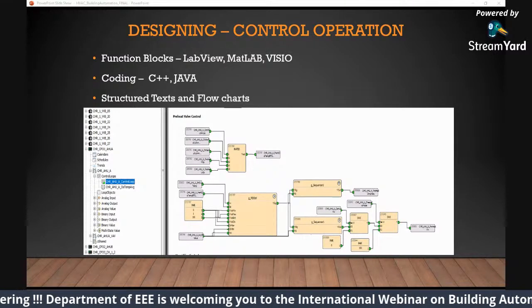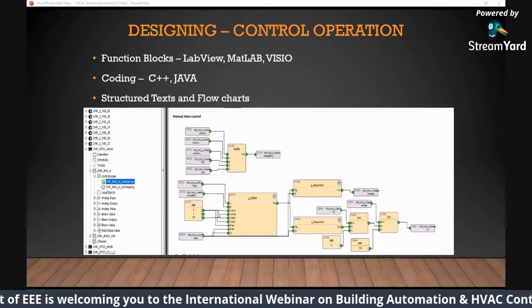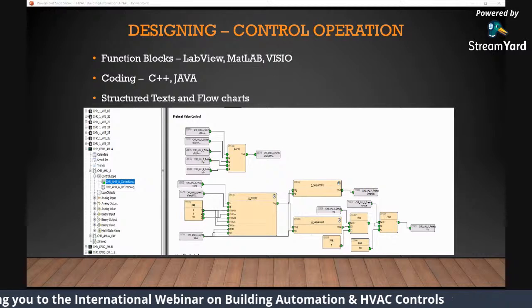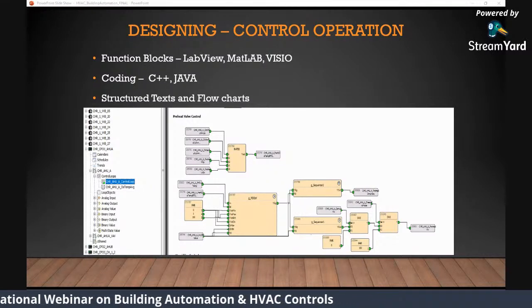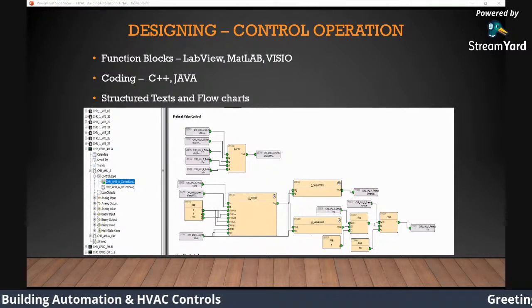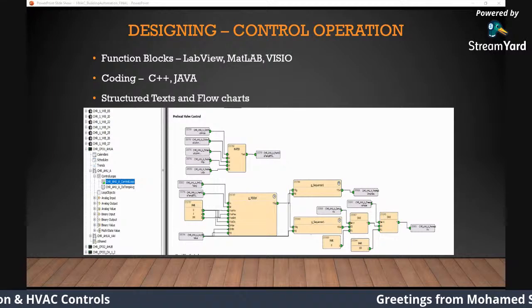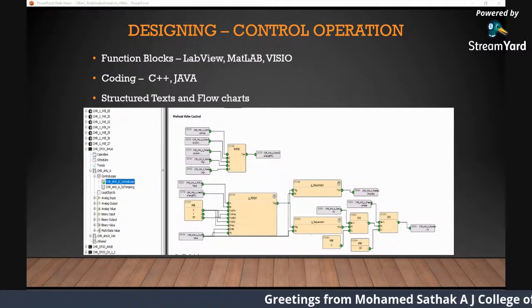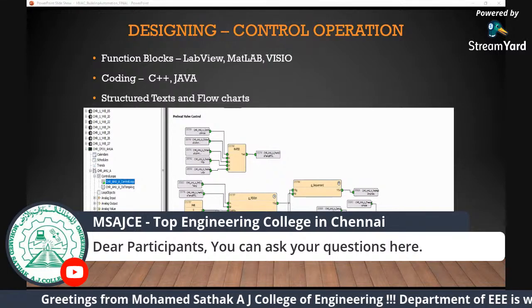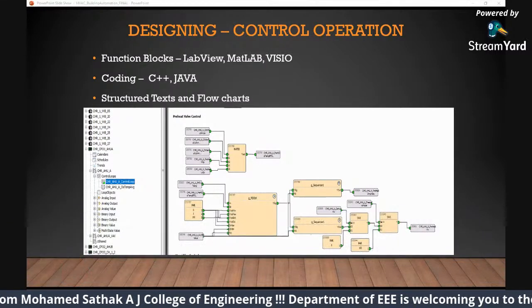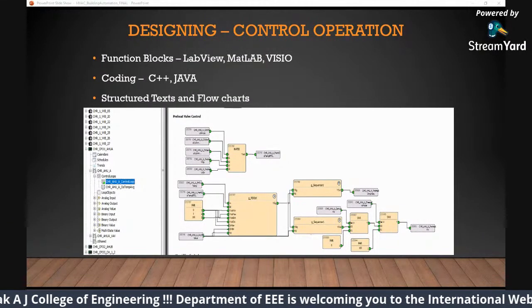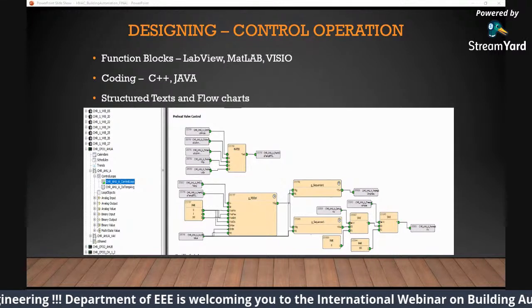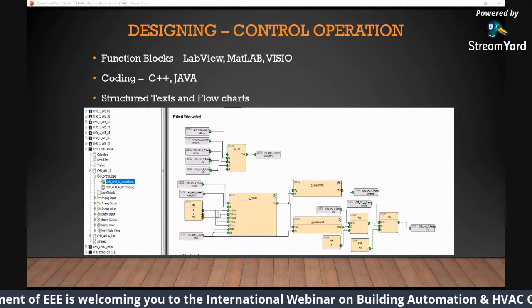And once you download into the controller, it's going to run on its own throughout. You don't have to monitor or operate. All you have to do is wire the inputs and outputs of the controller, design your sequence of operation, download into the controller, and that's it. It's going to take care of its own. That's how we call it AI. Artificial intelligence is nothing but once you design and download into the controller, that controller will measure your parameters and everything. That's it. Let's take an air conditioning unit as an example.